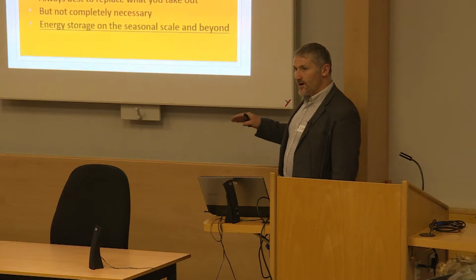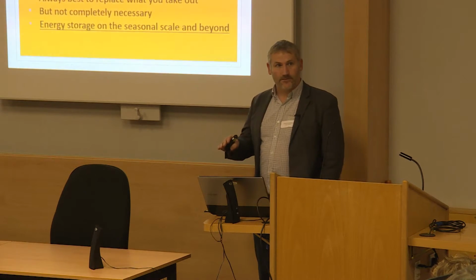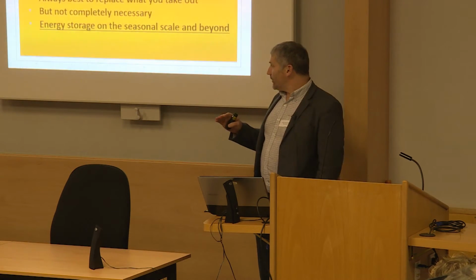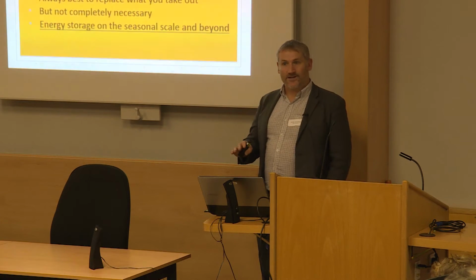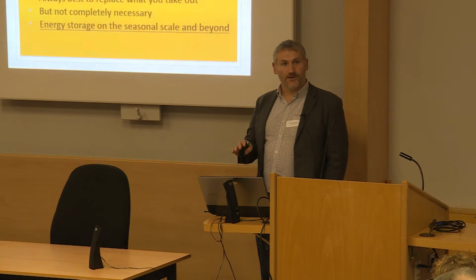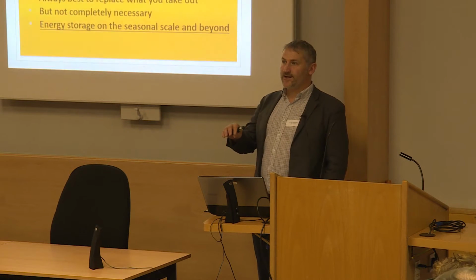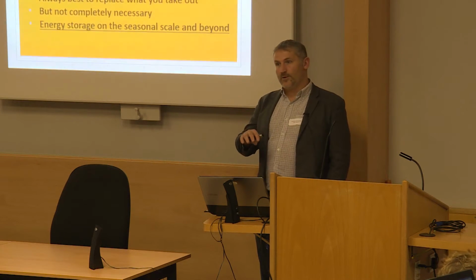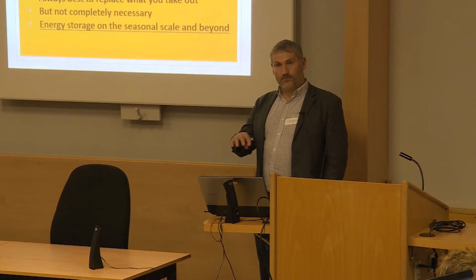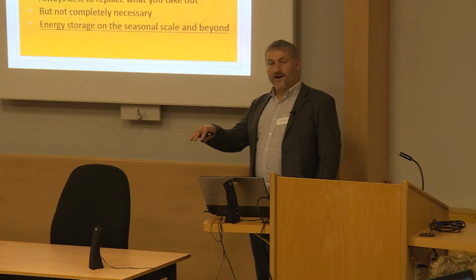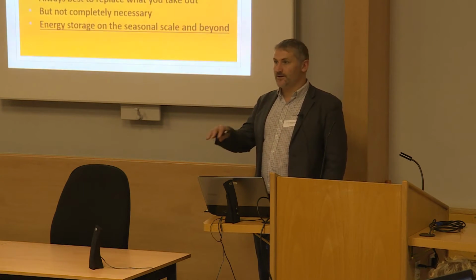One thing I would say about ground source heat pumps and systems like this: your energy storage is on a seasonal scale and beyond. So effectively what you're doing is taking heat out of the building during the summer and putting it in the ground, then taking it out in the winter. It's seasonal storage.